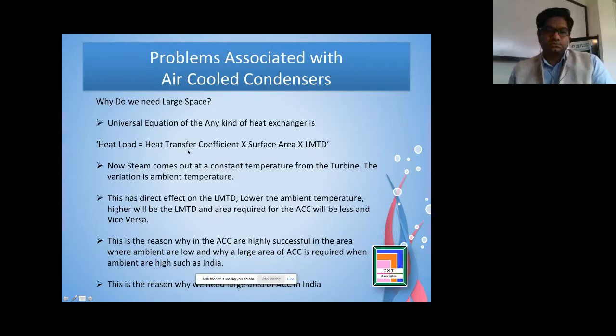Now what happens is, in the case of a lower ambient temperature, when this LMTD goes higher and the surface area is fixed, we have an option to change this U factor. The U factor can be changed by reducing the fan speed, so that at a lower ambient temperature we also save on energy. And once this crosses the design temperature, let's say we have designed a heat exchanger at 45 degrees centigrade. At 45 degrees centigrade, our LMTD is balanced out with the heat load.